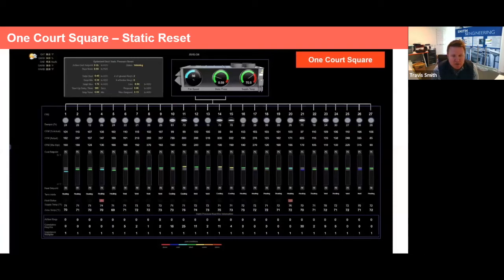This is one of the strategies right here. Here's an ASHRAE 36 static and SAT reset. You can see the little circles there are the VAV box damper positions out on the floor. So this does a trim and respond based on damper position to constantly reduce the static pressure set point. I think ASHRAE 36 does a good job of laying out the guideline, but implementing it in a practical way that is not overridden by the operator really takes a lot of experience. And the team here had a lot of experience doing that.